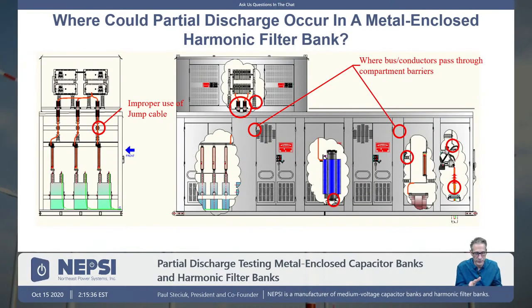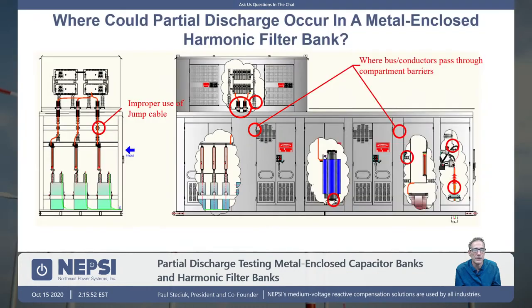We also have multi-compartment systems. It's a compartmental design, and we do that because we're looking to segregate compartments for isolation, sometimes for safety getting in and out, but also sometimes for thermal reasons, to isolate the hot components from the cold components. So where we're passing from one compartment to the other, this would be a location. We have pass-throughs, kind of like that picture I showed you earlier. It's important that those pass-throughs get done correctly. If they're not, you'll get partial discharge at those locations.